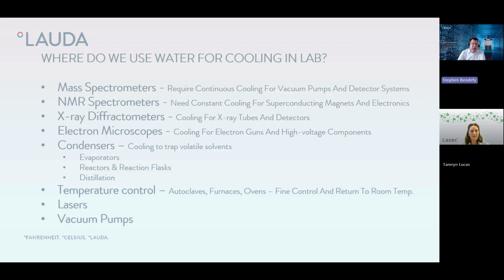They're also used to provide some level of cooling for other apparatus associated normally with heating. So, for example, some autoclaves, furnaces, ovens have a water supply to balance against that heat that's being provided by the electrical heating, and that provides some fine control, particularly at the lower temperatures.